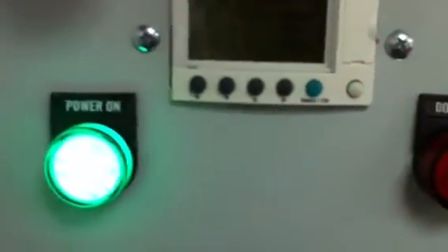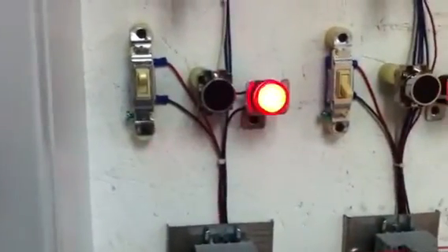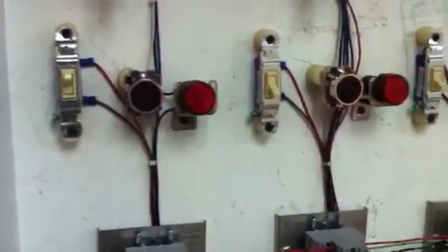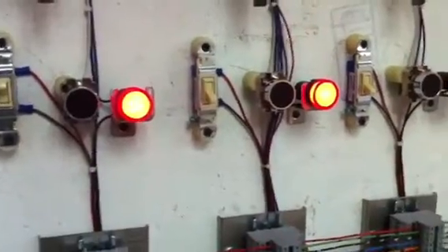So a couple of hints: if you don't want to hear that buzzer, but you want to mute it, you press this button. The 4 is shown over here, that's 1, 2, 3, and 4. And the system will not sound again, but the alarm will remain on because we still have that condition in there. What's going to happen instead? The display of the panel is going to start blinking. I'm sorry. So during this time, no door can be opened because there's an issue on door number 1.